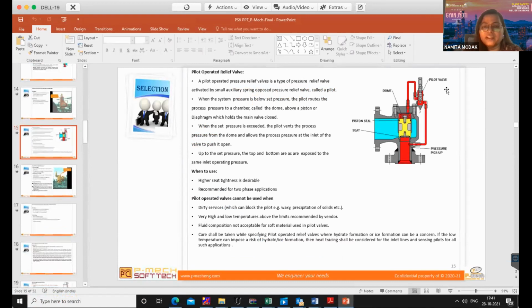Yes, that is right. The arrangement is one. So it is not like the pilot is discharging separately and the main valve separately. No, both of them are connected to the outlet line. The blue one which you can see is the outlet line. Yeah, but this is the normal scenario when the PSV has not popped. No, but when your PSV pops up, right? Normally there is no flow in this blue line.